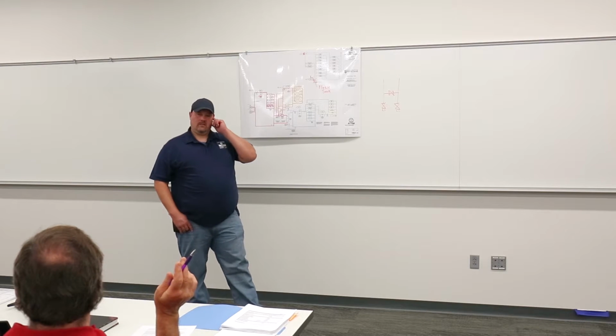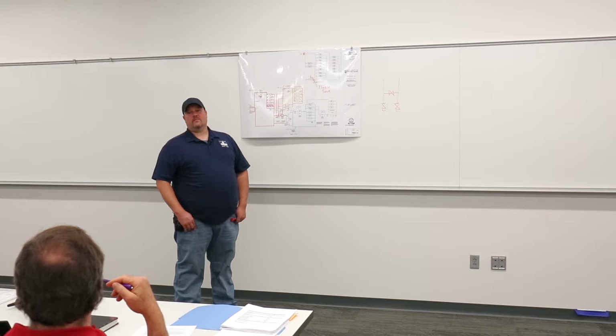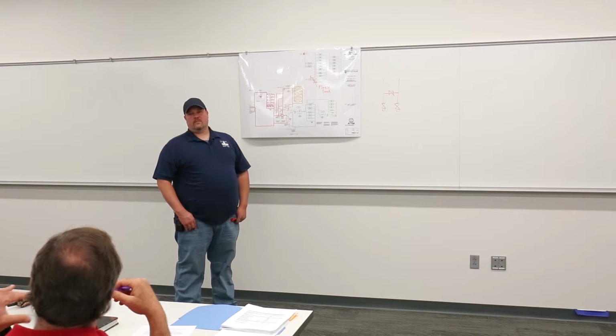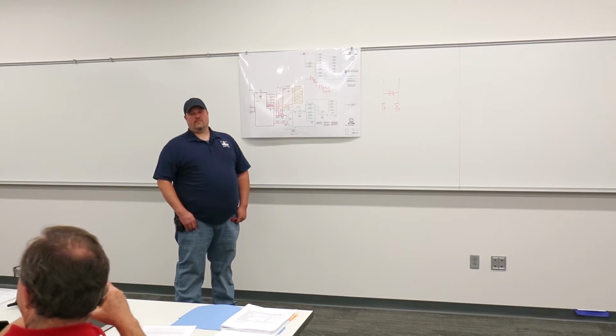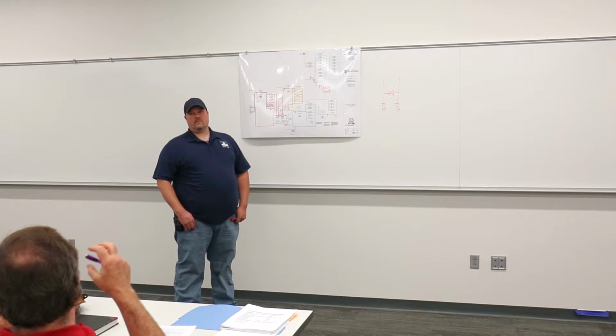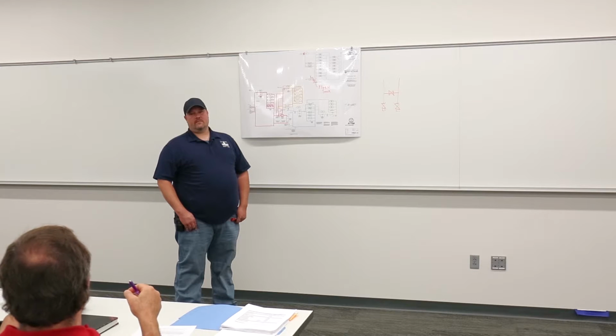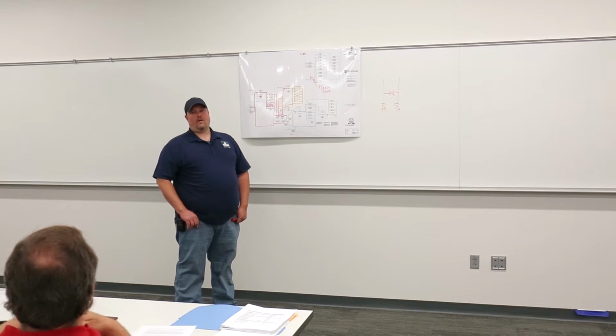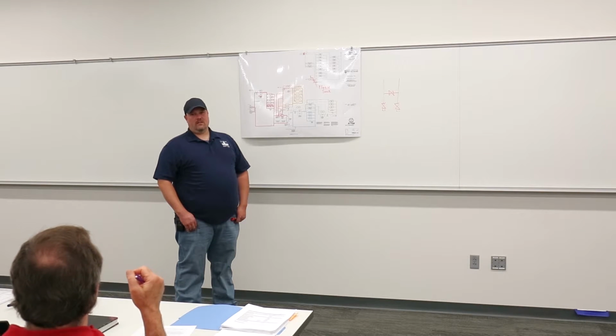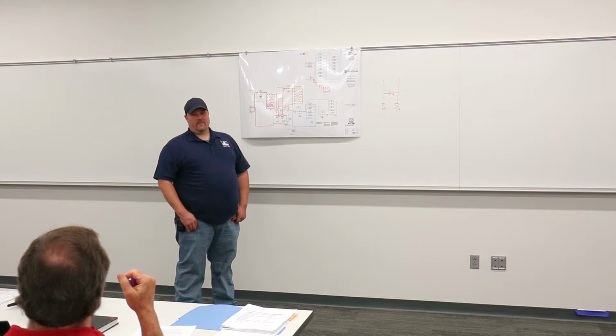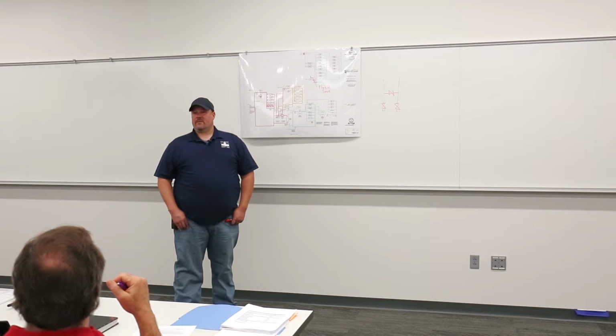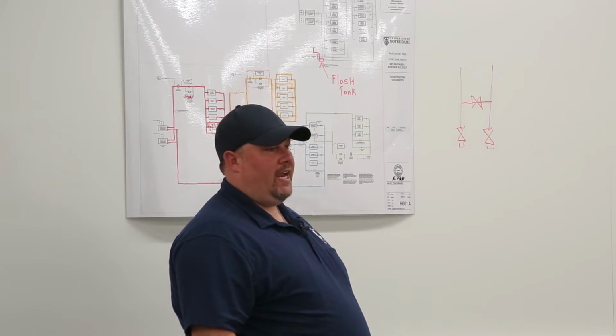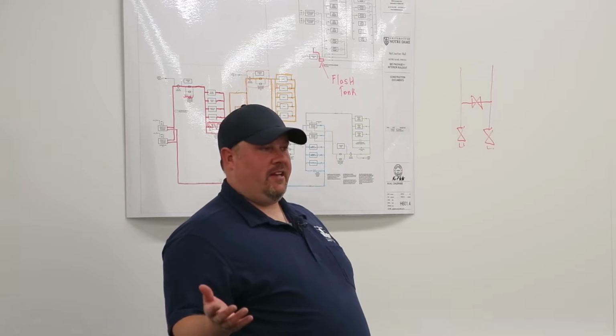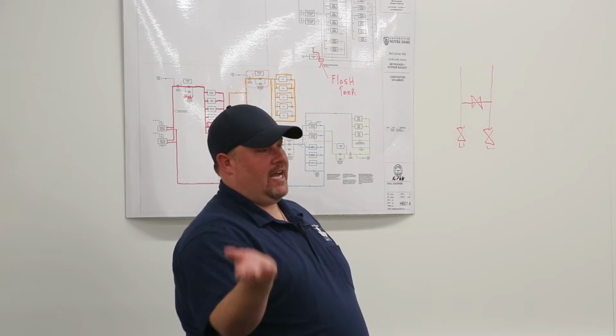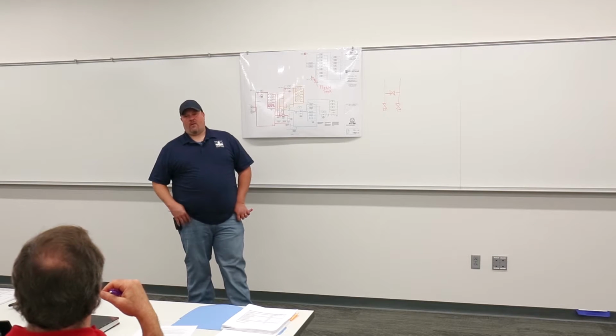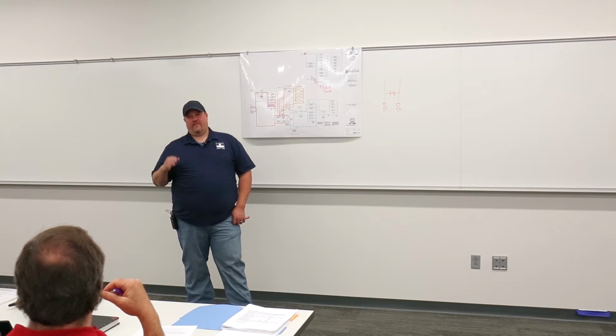Yeah, and what we have happen, like at Stinson Remick, we have the old level control, and the tank is constantly flooded because system pressure is always higher. So it effectively never makes up. We actually have an automatic valve on the expansion tank that opens it when we shut down chilled water, but it never works, because the pressure is always high, and so it always floods it. Yeah. You'd have to set that pressure like 80 pounds or something in order to make it work. As we notice, it's got our gauges pegged on our pumps because it is so high. We're on a 0 to 100 range, and as it comes in the building at 65, 70 something PSI, and then it goes out of the pump, you get that boost of an extra like 30 PSI on it. So yeah, they're right at like 90, 95. Yeah, so they're within the range.